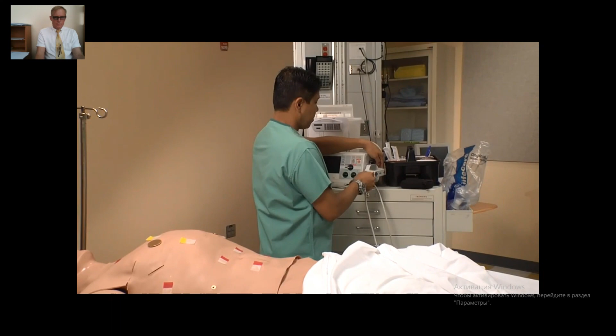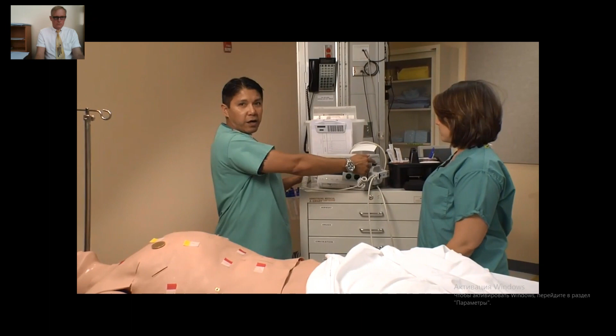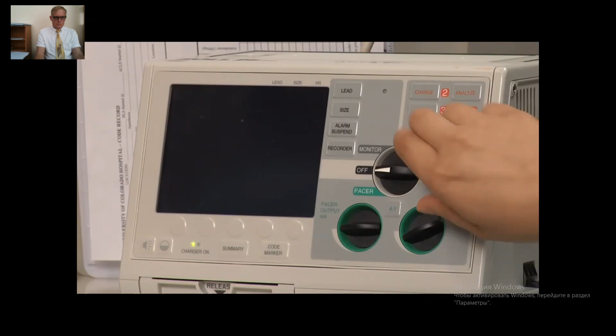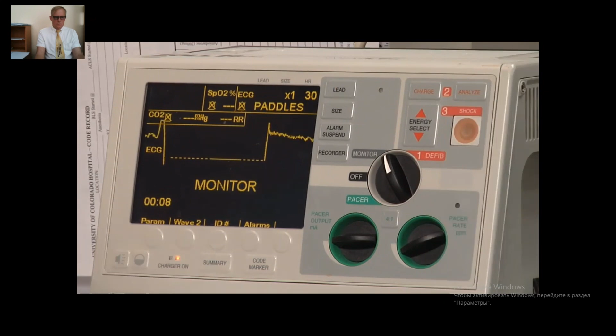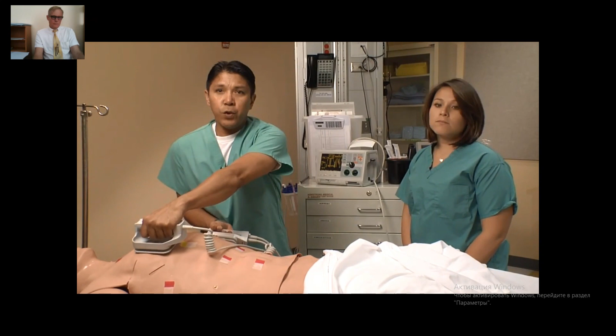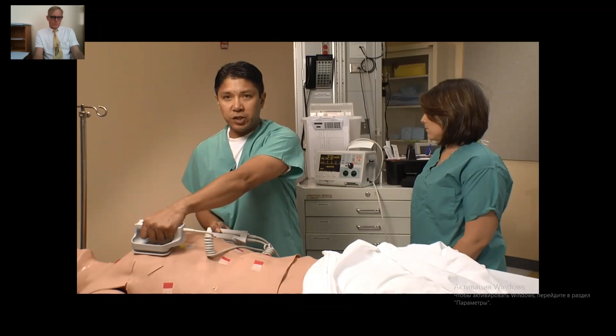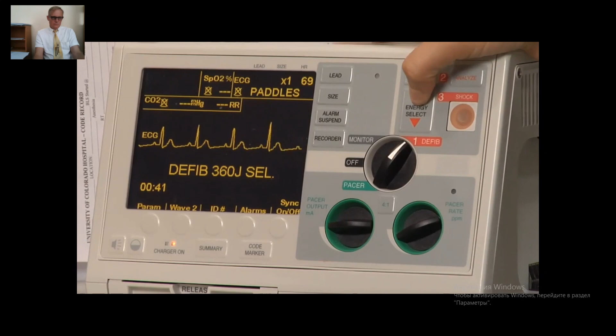When using the defibrillator, the left paddle is placed on the sternum and the right on the apex. Effective use of the monophasic defibrillator requires 2 individuals. Release the paddles from the defibrillator by using the release mechanism located on the left and right side of the defibrillator. Turn the main dial clockwise and select Monitor. Press the lead button until the word paddles appears on the screen. Place one paddle on the sternum and the other on the apex. View the waveforms on the defibrillator monitor.